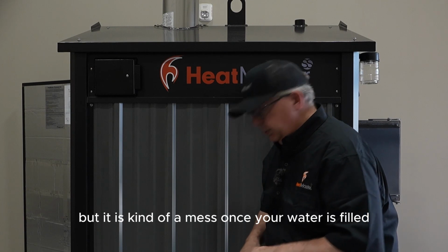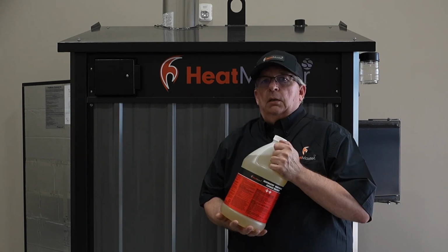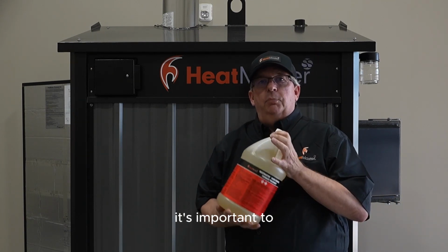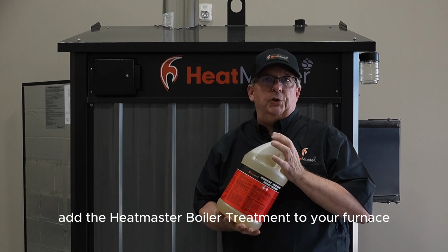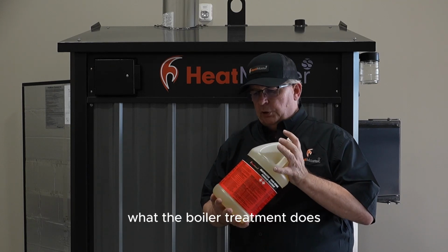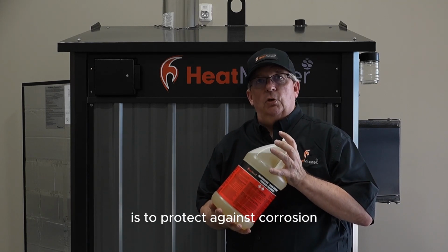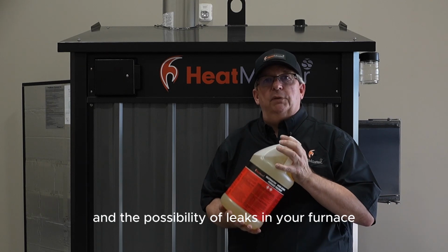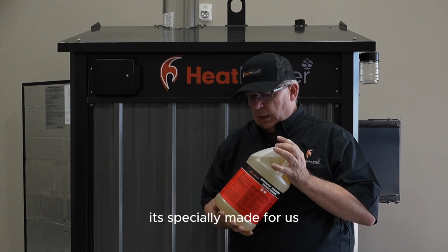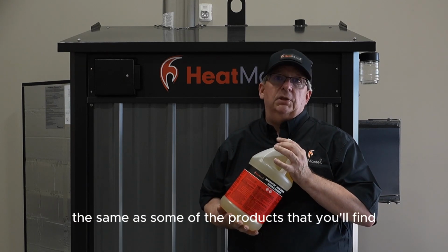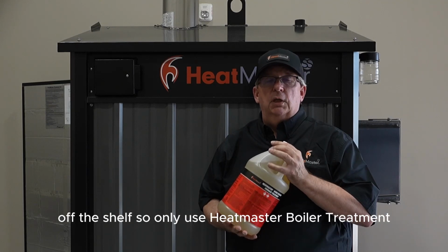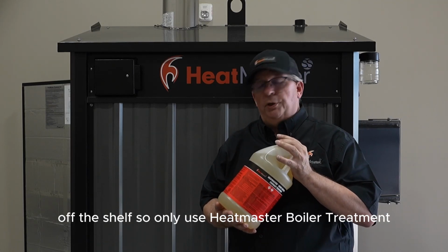Once your water's filled, the next step is critical. In order to maintain your warranty, it's important to add the Heatmaster boiler treatment to your furnace. What the boiler treatment does is it protects against corrosion and the possibility of leaks in your furnace. It's specially made for us and not the same as some of the products that you'll find off the shelf. So only use Heatmaster boiler treatment.